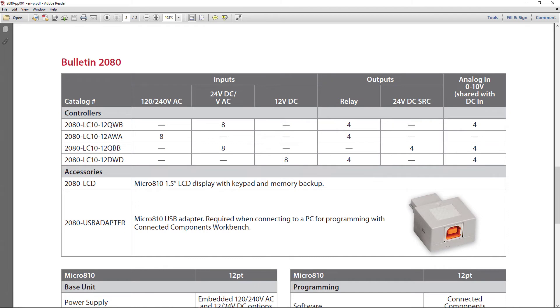And those four analog inputs share the same terminals of four of your eight inputs. So if you were going to do four analog inputs, that would leave you just four digital inputs. And by the way, there's the USB adapter right there that plugs into the top of that.